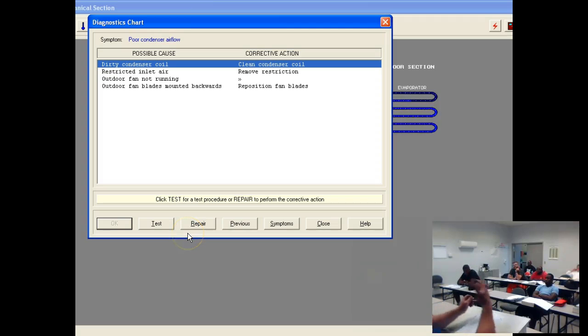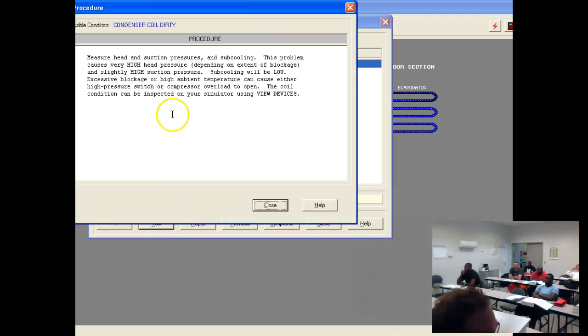Because if you just do the repair, you're not really learning. Now, sometimes there's not a test. But you need to get good enough with this program to already know what the test is. Like, well, this is what I would do to fix it. So this is saying dirty condenser coil. What do y'all suspect dirty condenser? Before you go and clean it, what do you think the test for a dirty condenser coil may be? Test. Measure head and suction pressures and subcooling. This problem causes very high head pressure.